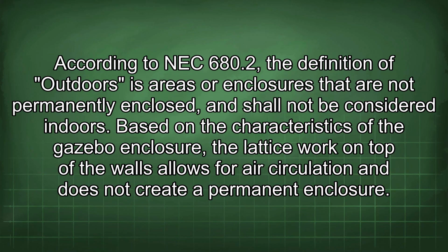According to NEC 680.2, the definition of outdoors is areas or enclosures that are not permanently enclosed and shall not be considered indoors. Based on the characteristics of the gazebo enclosure, the lattice work on top of the walls allows for air circulation and does not create a permanent enclosure.